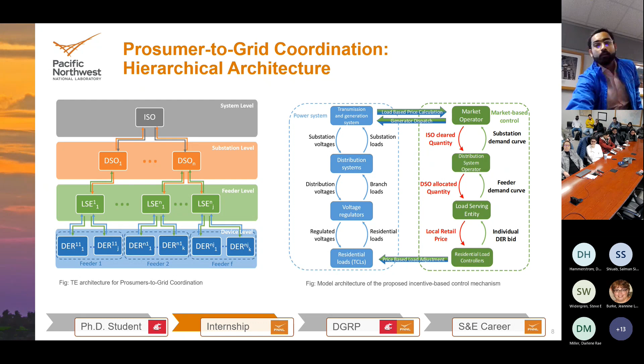That's the market side. On the physics side, residential loads set their consumption, which changes branch loads and substation loads, going up to the transmission level. This affects substation-level and distribution-level voltages, finally causing tap changers and capacitors to act to regulate distribution, customer, and service-level voltages.